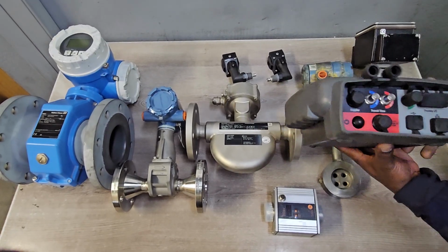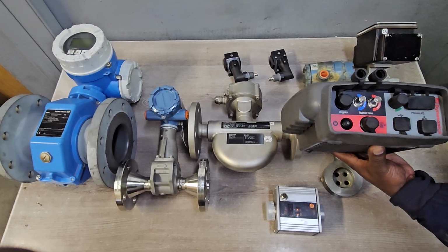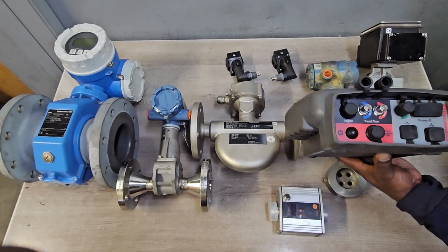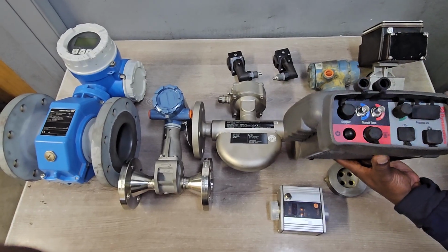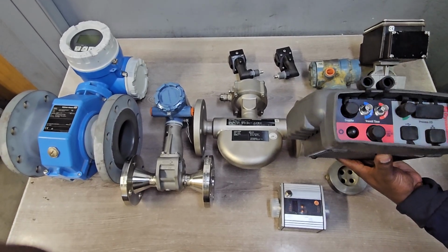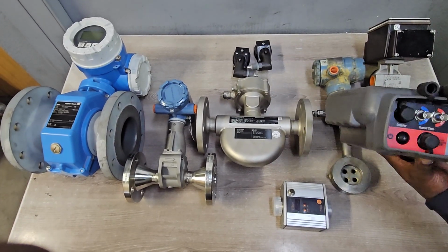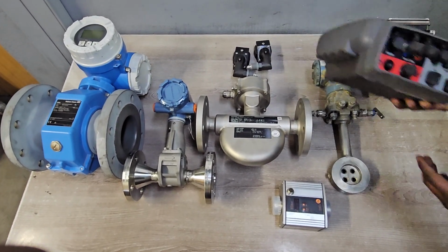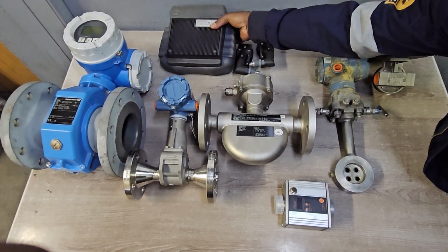But there are other values that you enter on the flow meter, such as the pipe size, the thickness of the pipe, the material, and the density of the material, depending on whether you are measuring a liquid like water, or slurry, or an acid. Remember, in industry there are different types of liquids being monitored. But that's another type of flow meter. It's called an ultrasonic flow meter.